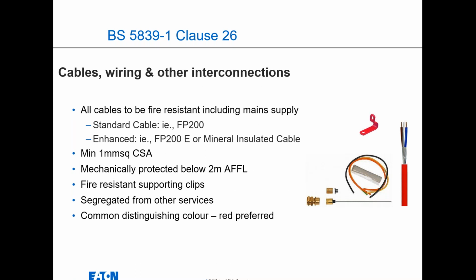Cables and other interconnections all need to be fire resistant. That includes the main supply, whether using the network cable or the loop cables. So you've got standard cable and enhanced cable. And as I say, mostly the loops can be generally in standard cable, but any networking perhaps needs to be done in enhanced cable, because basically the system integrity needs to remain there across the network as opposed to the local loops.